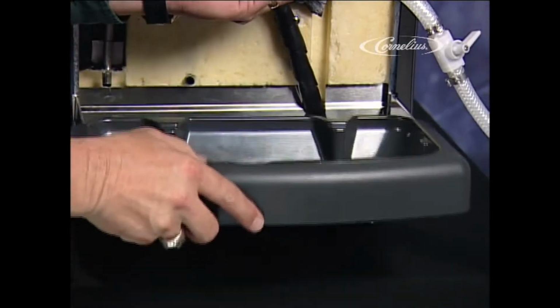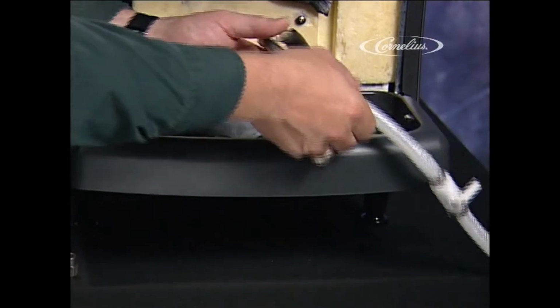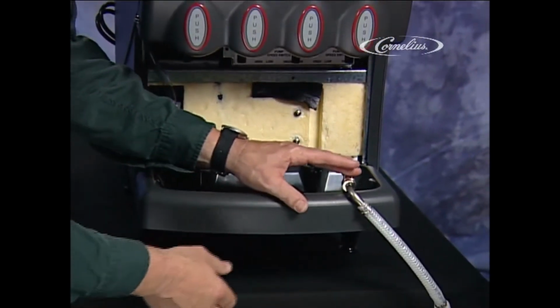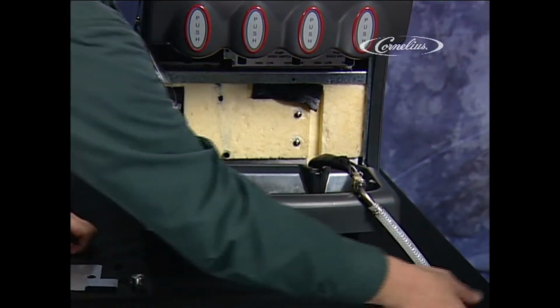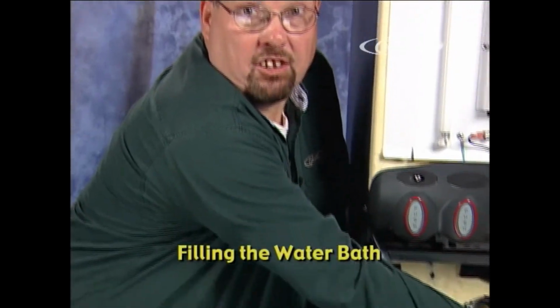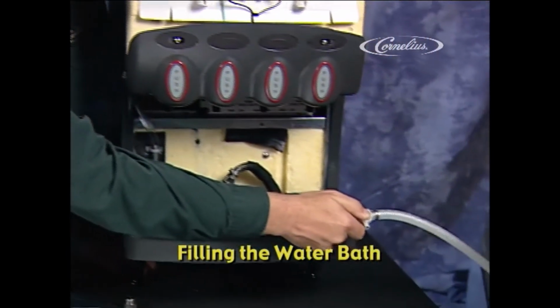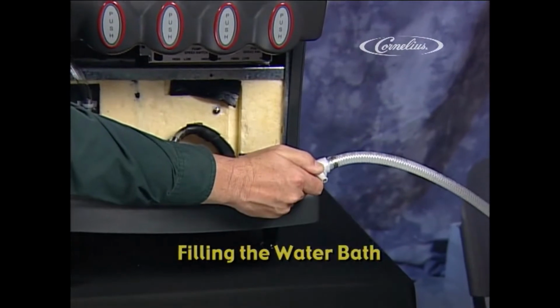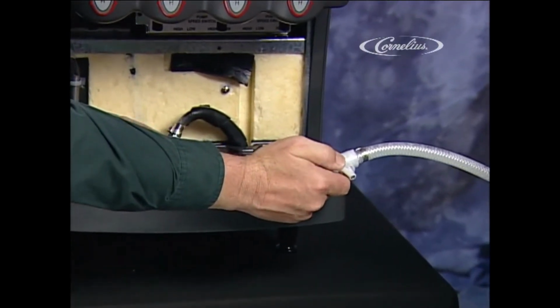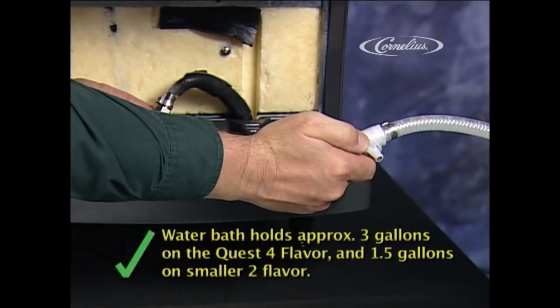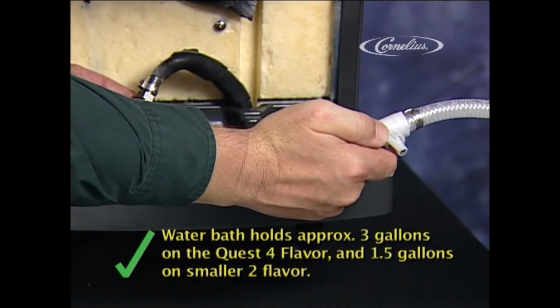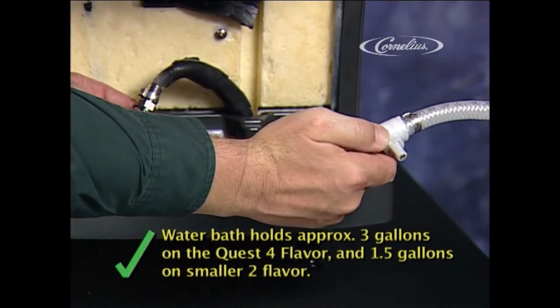It is advisable to mount the drip tray to catch the overflow when the water bath is full. Now we are ready to fill the water bath. Begin by slowly opening the shutoff valve, and continue until it is opened all the way. Fill the water bath until you see water begin to run out the overflow. The water bath holds approximately 3 gallons on the Quest 4 flavor and 1.5 gallons on the smaller 2 flavor.